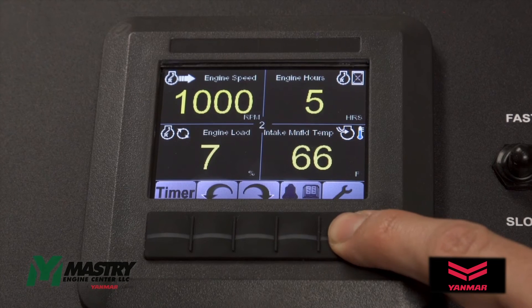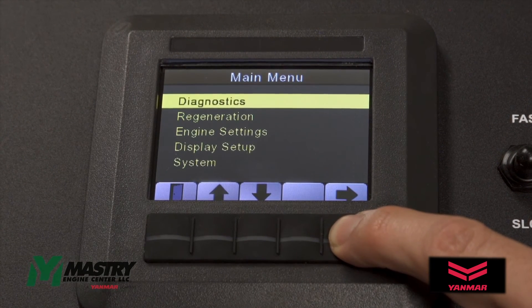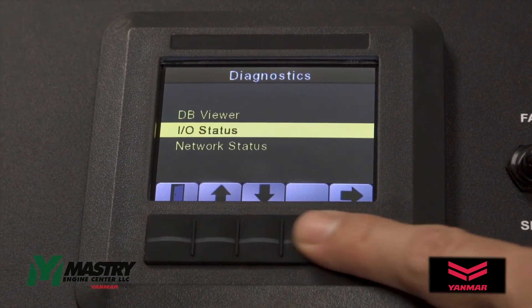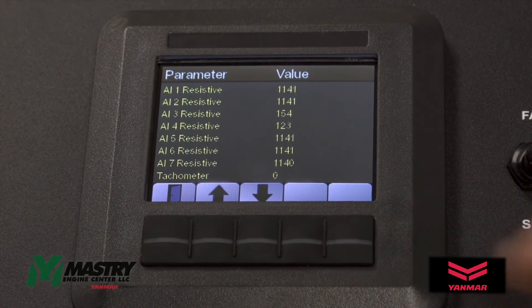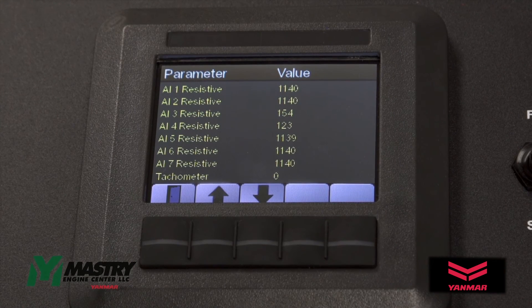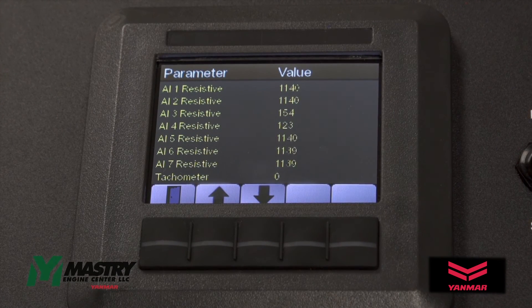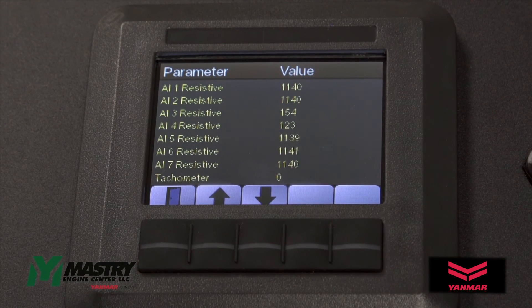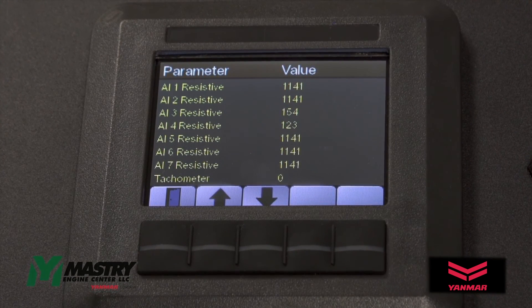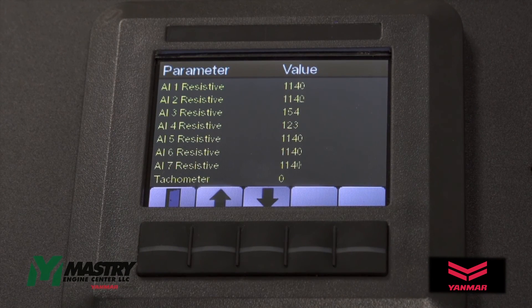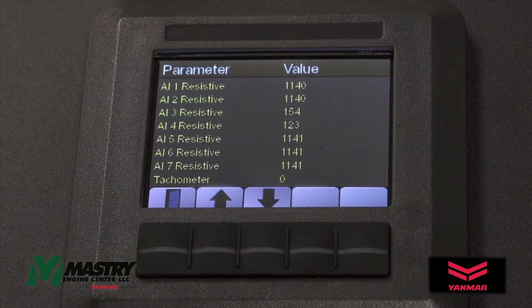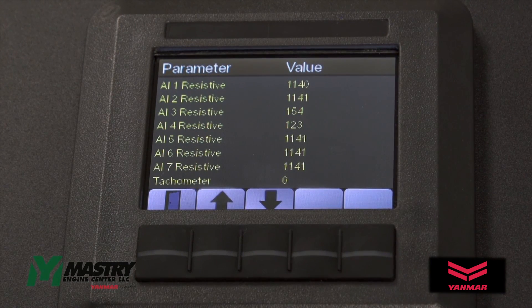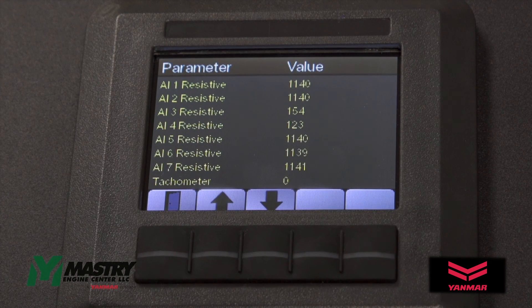To get more information about the analog inputs to the panel, enter the main menu, then the diagnostic menu, and then I-O status. Analog input 3 is the fuel sender, and analog input 4 is the oil pressure sender. Analog input 3, the fuel input, should read between 33 and 240 ohms if it is functioning correctly. Analog input 4, the oil pressure, should read between 10 and 180 ohms if it is functioning correctly.